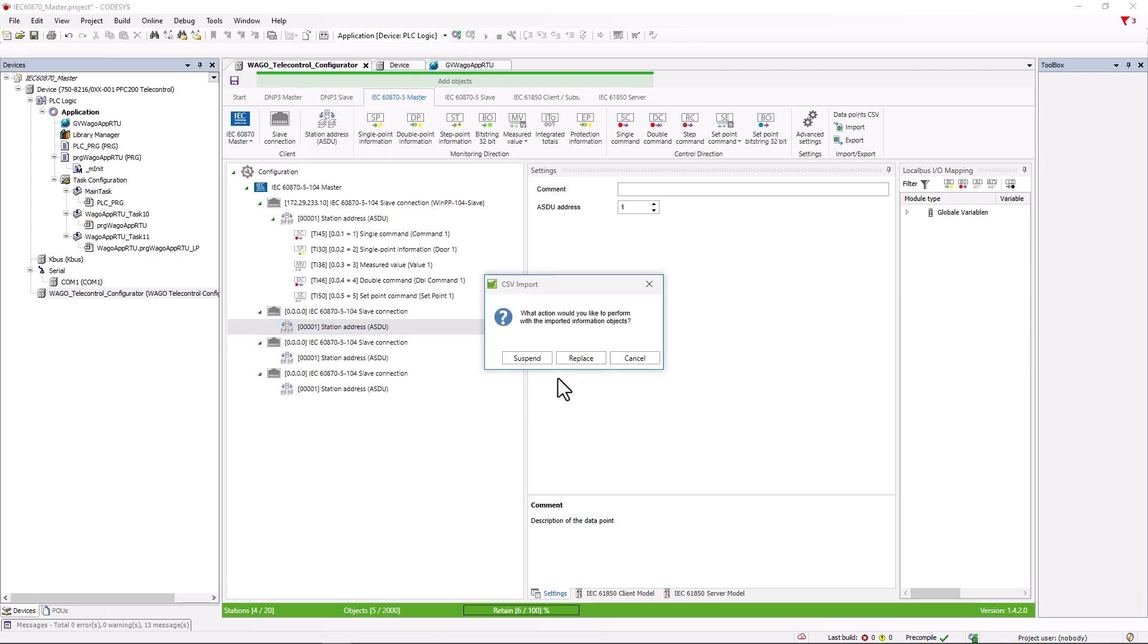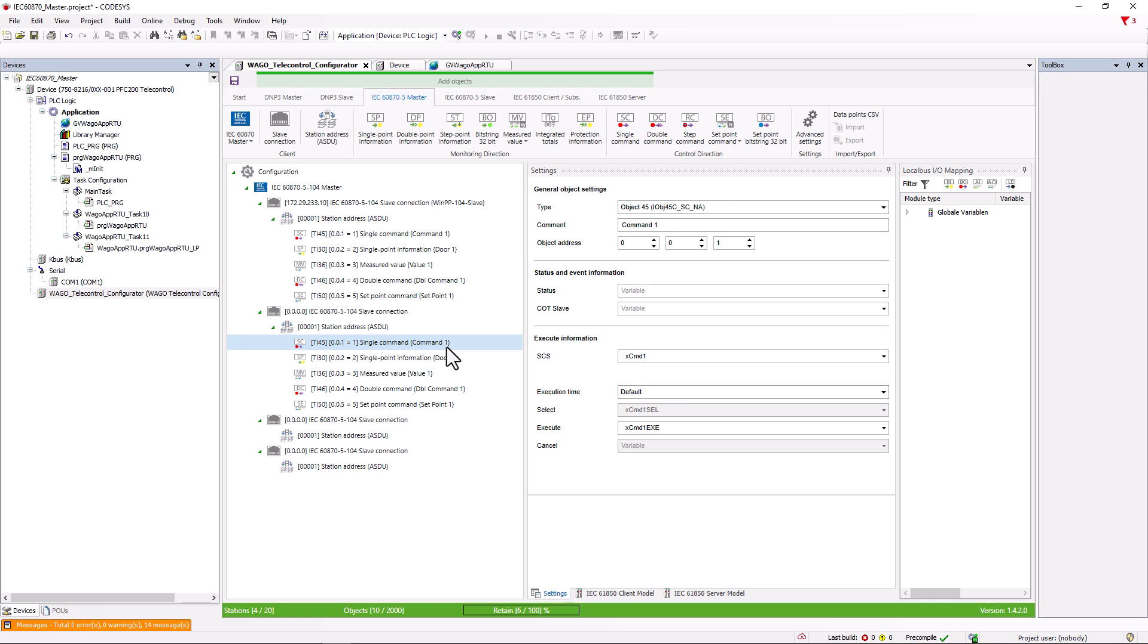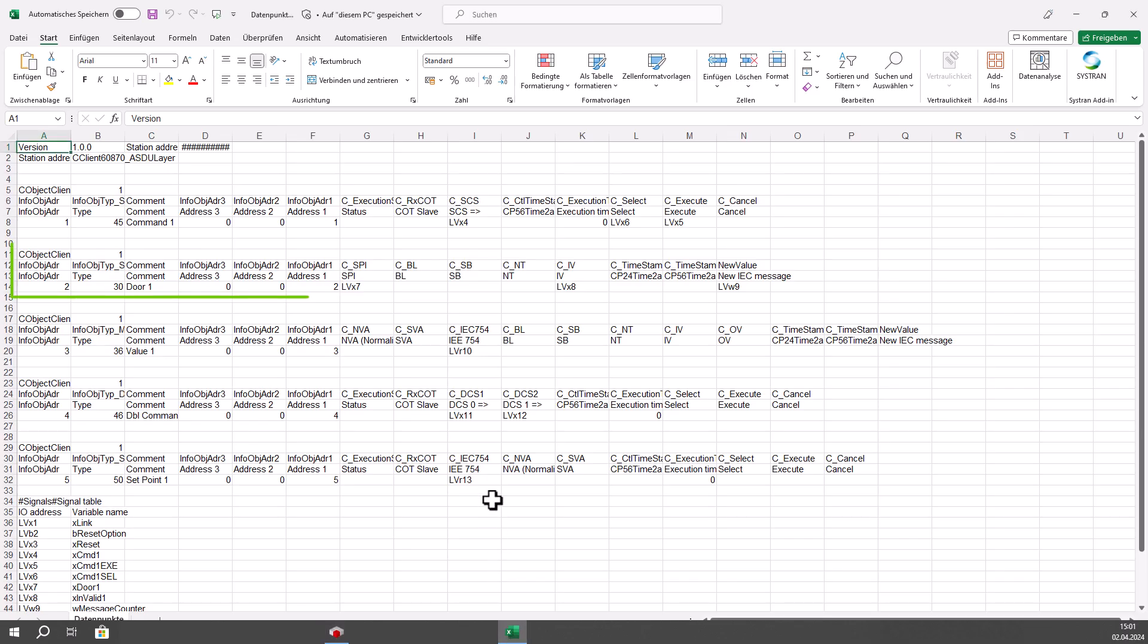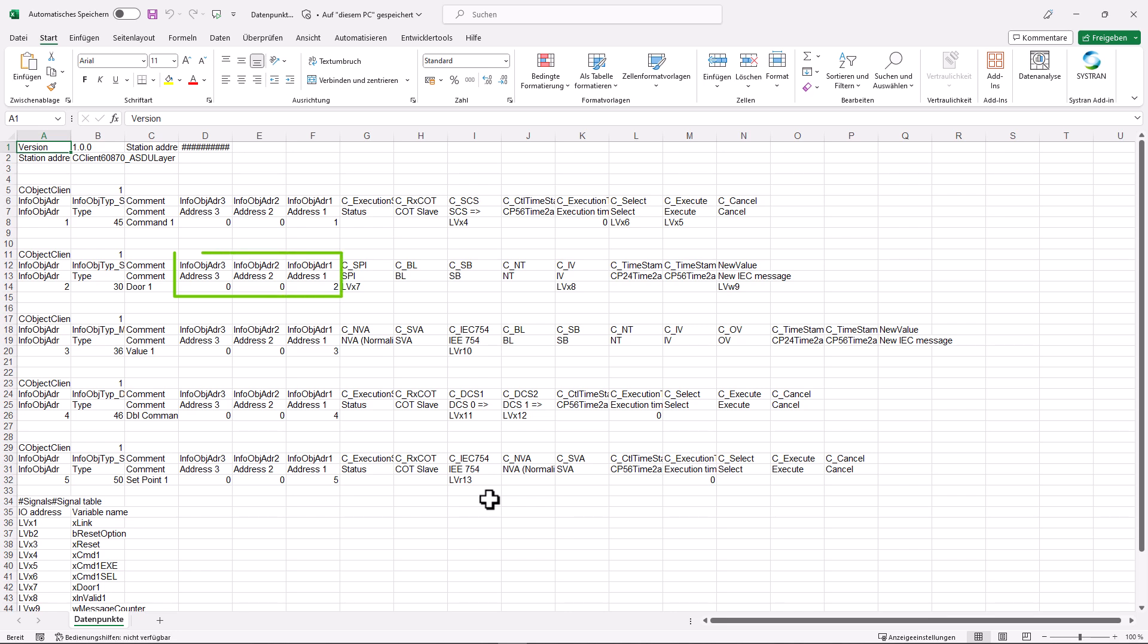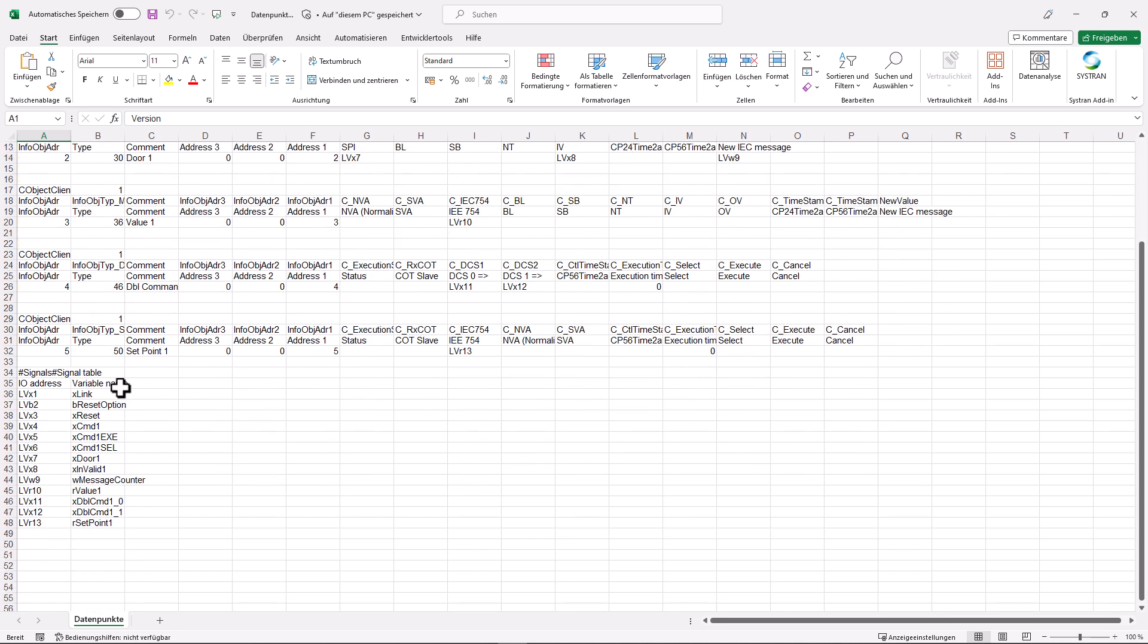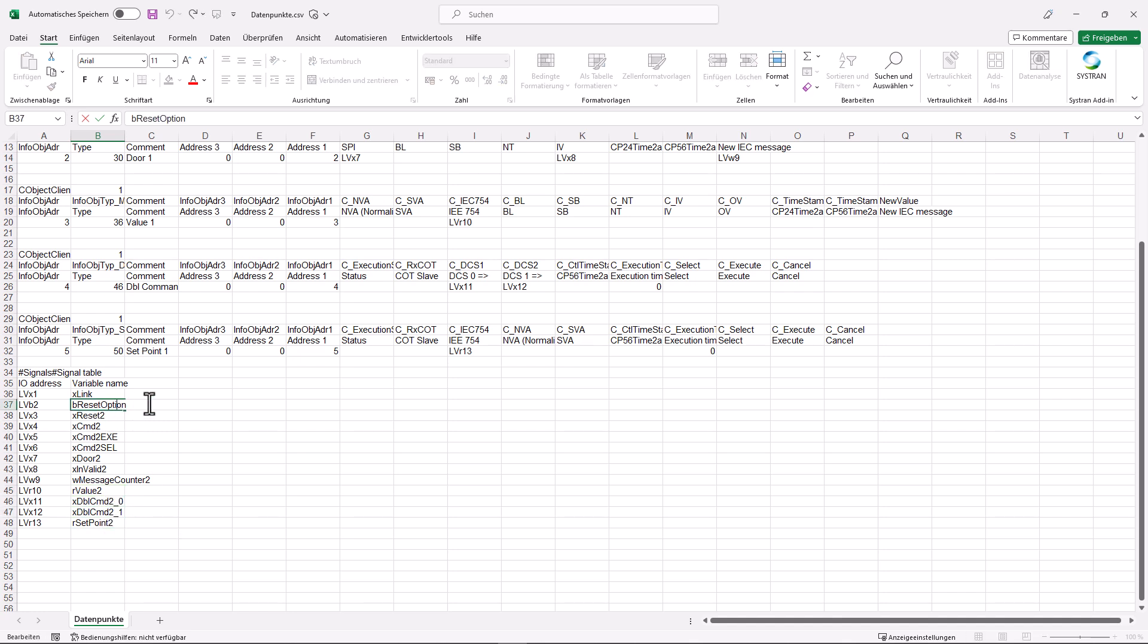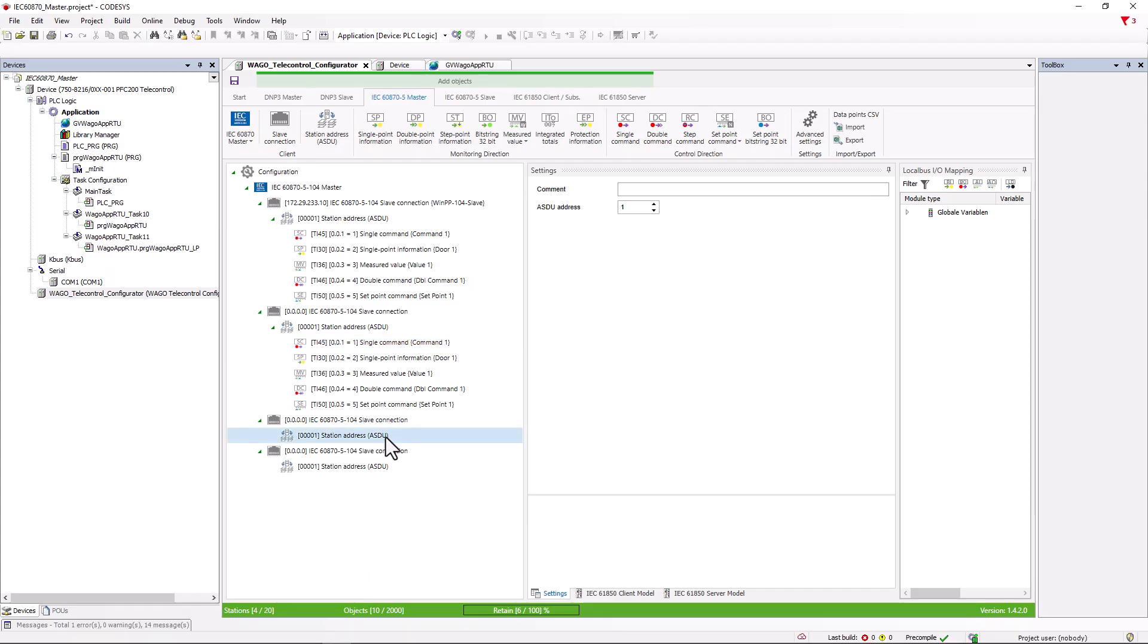All data points will be transferred, as well as the variable names, which now need to be changed. It may be helpful at this point to edit the CSV file directly before importing. When you open it, such a block is always a data point. Here is the type identifier, here is the object address, and here are the variables. One for the single message and one for the IV bit. The variable names we have assigned are also assigned to the abbreviations at the bottom of the table. We can now edit, save and import these accordingly. The new variable name can either be changed here in the assignment table or directly in the data point block.